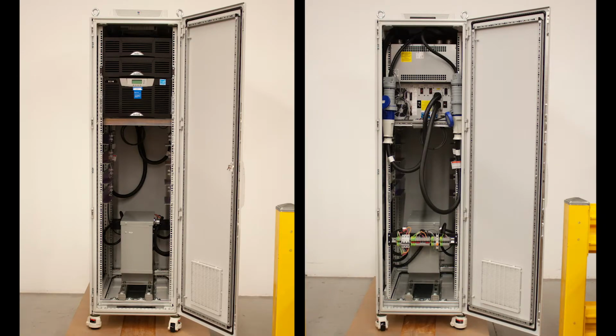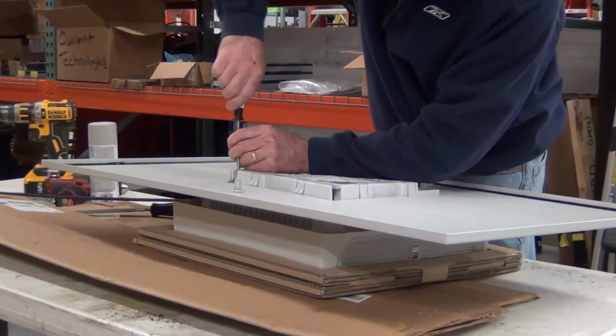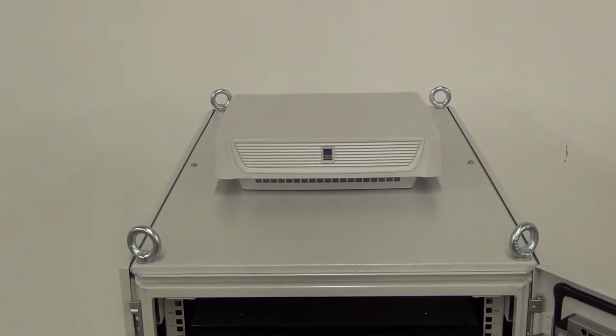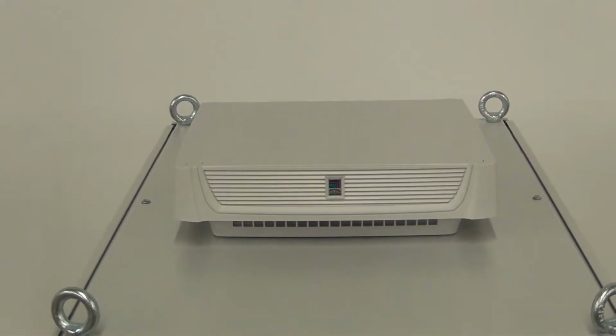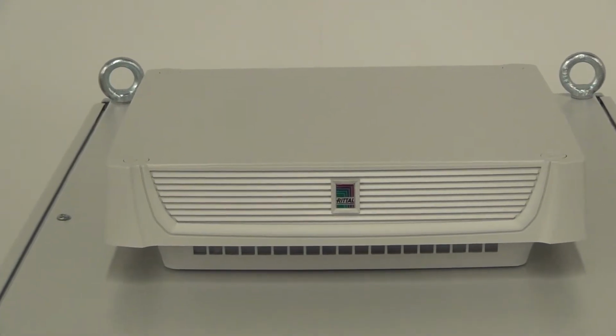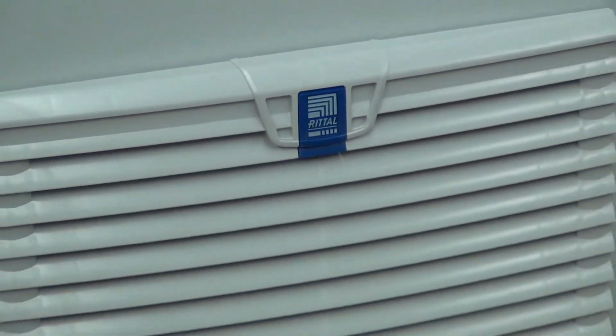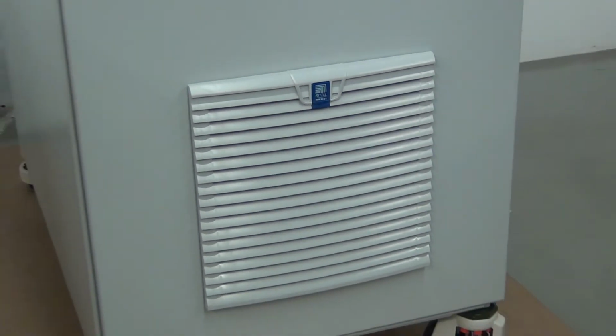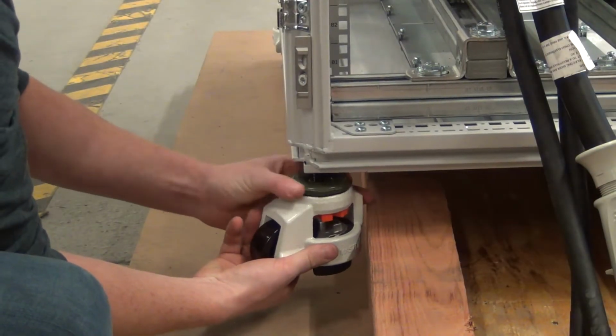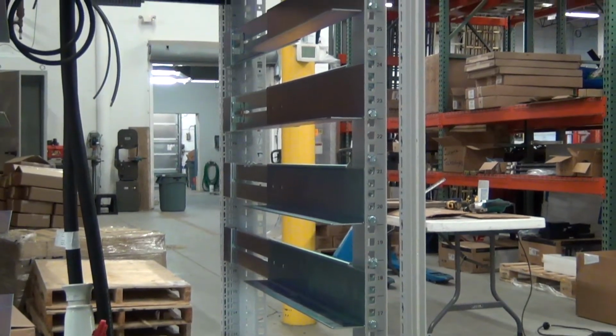Removable doors on the front and rear of the enclosure provide easy access to installed equipment, as well as clearances needed to service the UPS and battery system. The doors and roof were modified to mount intake filters and a high-velocity 589 CFM ventilation fan, which provides the airflow needed to keep the temperature within the manufacturer's recommended limits, and also exhausts any hydrogen gas vented by the battery system. Our team then added heavy-duty caster leveling feet assemblies and mounting rails.